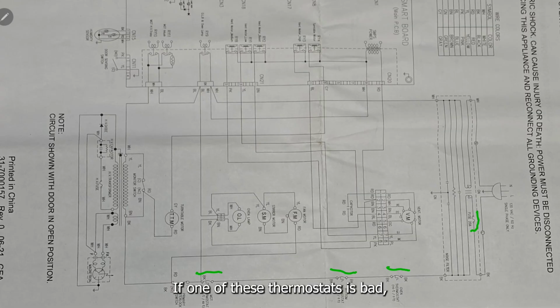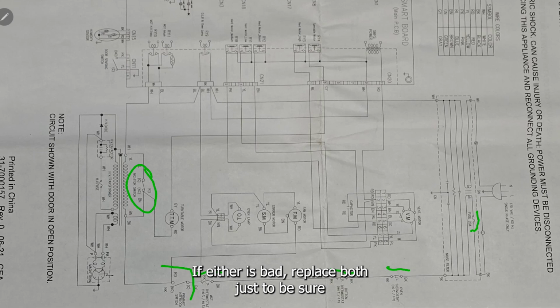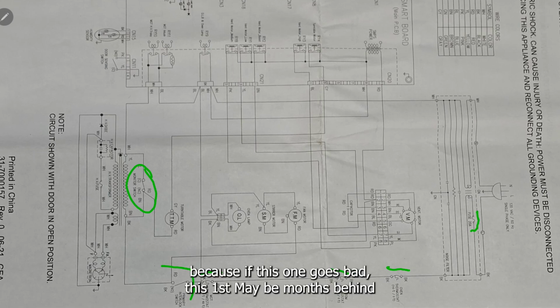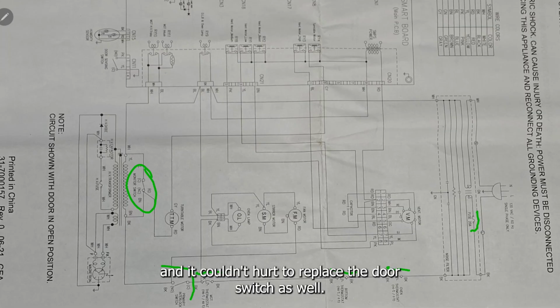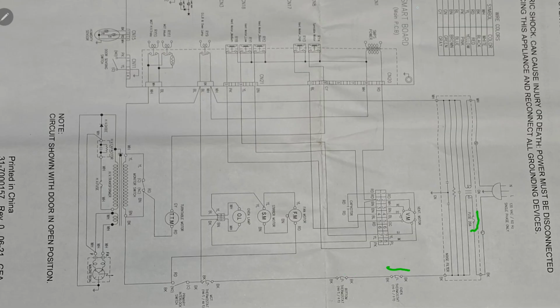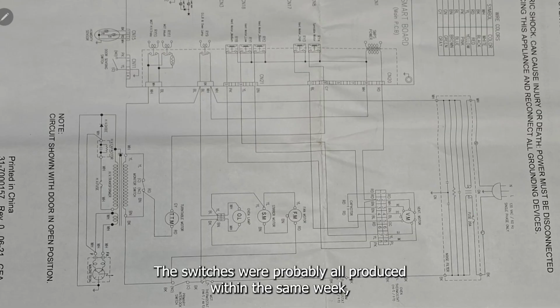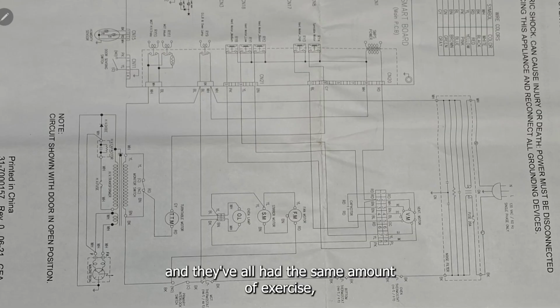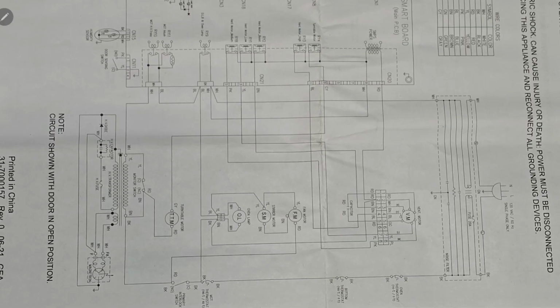If one of these thermostats is bad, the first thing to check would be the main interlock switch and the monitor switch. If either is bad, replace both just to be sure, because if this one goes bad, this one may be months behind. And it couldn't hurt to replace the door switch as well. These switches were probably all produced within the same week, and they've all had the same amount of exercise. So if one goes bad, the other two may not be far behind.